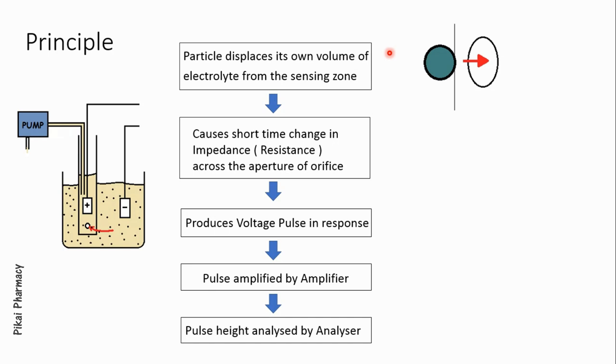It is constructed so well that only one particle can pass through at a time. When a particle enters the orifice, it displaces its own volume of electrolyte, and this causes a short-time change in impedance, or you can also say a short-time change in the resistance across the aperture of this orifice.